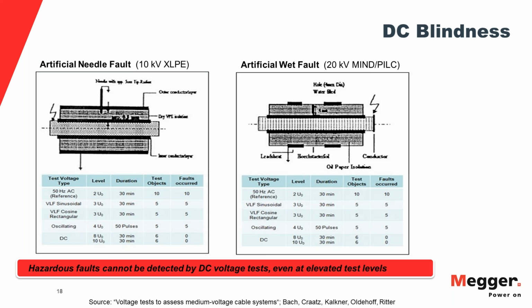Now, a result that wasn't really expected by the people working on investigating these first, second, third generation polyethylene cables: they also put the different voltages up to the test to see if they are able to find faults or fault conditions. And the result is stunning. As you can see, the DC test scored 0 out of 12, both on the XLPE cable and the PILC cable.